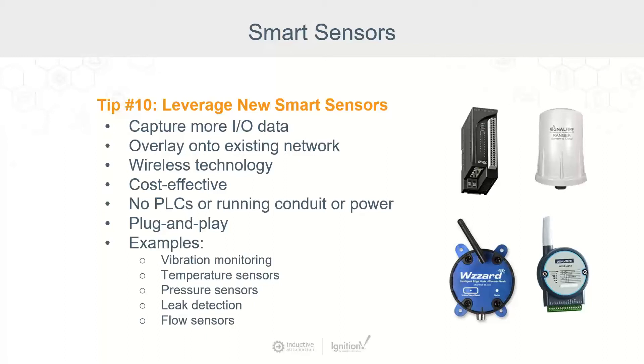People are already leveraging these things. You don't have to spend time configuring them — you can just hook them up and start leveraging that data very quickly and easily, and also very cost-effectively. A lot of times we're not running conduits or power, and we're not having to wire to a PLC and then program PLCs. Common examples include sensors for vibration monitoring, especially to predict machine failures, and temperature and pressure sensors.